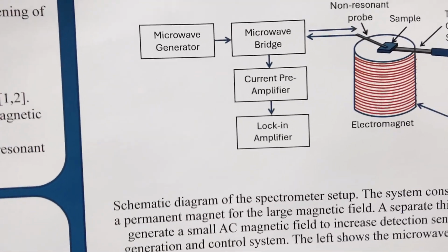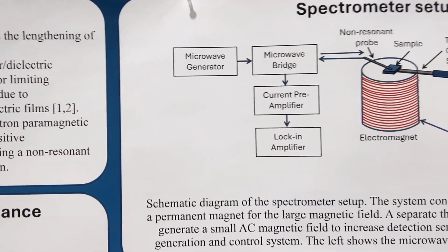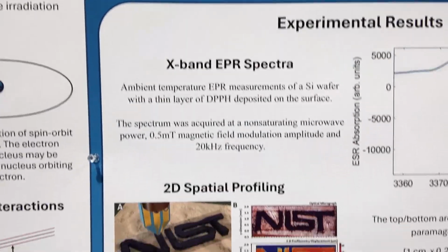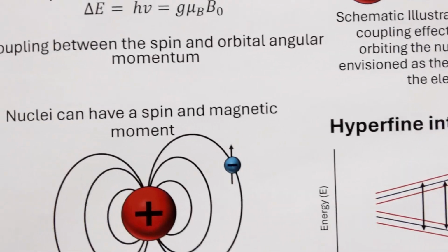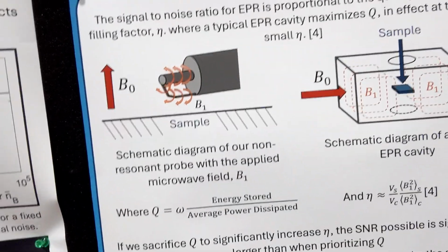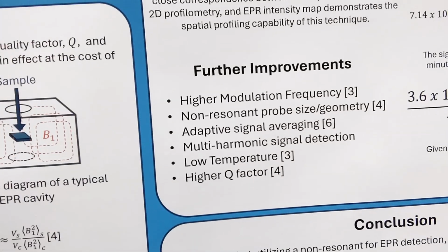Yeah, so what we're using is EPR, electron paramagnetic resonance. And so electron paramagnetic resonance is very popular for detecting paramagnetic spins, right? So these spins that are causing the flux noise. But typical state-of-the-art, like the commercial state-of-the-art, can only detect about 10 to the 10 spins in a sample. But with our method, what we do is instead of using a cavity, microwave cavity, to send our microwaves in, and then what happens is the microwaves are absorbed by the paramagnetic spins, and then they flip spin, which then causes a change in the power of the microwaves in the cavity, and then we detect that change in the microwave power. But instead of using a cavity, what we've done is use a small non-resonant probe.